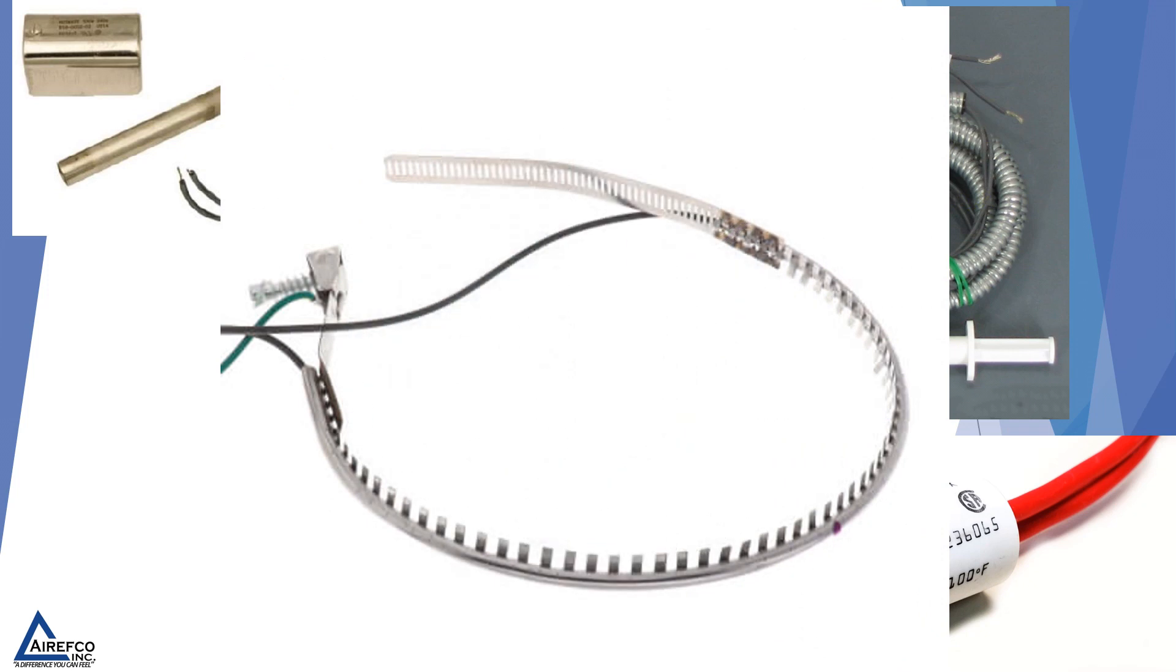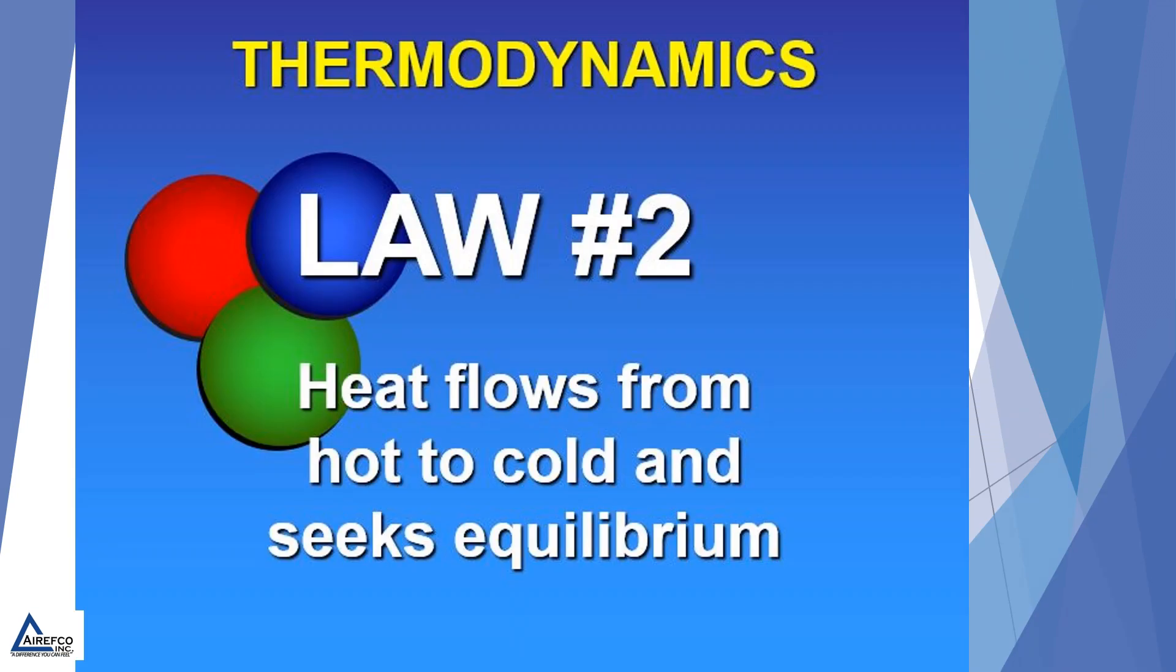You're going to see these on residential heat pumps and air conditioners. The reason that we want to have crankcase heat on a compressor is due to thermodynamics. If you've taken a refrigeration class recently, you would have been taught the second law of thermodynamics, which says that heat flows from hot to cold and seeks an equilibrium.